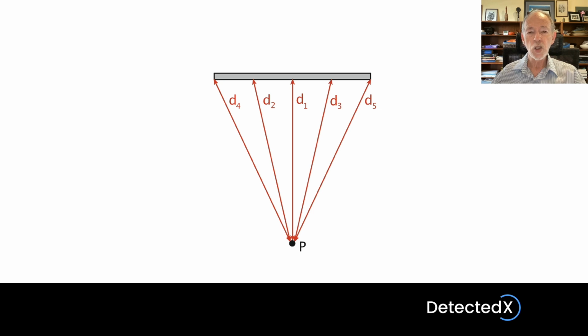Now let's think about geometry. Suppose I have a linear probe, and I am transmitting from different points on the face of that transducer, and I want to focus at the point I've labeled P. If I transmitted from every point on the face of the transducer at the same time, the ultrasound would travel along different paths to get to the point P. And I've labelled these path lengths D1, D2, D3, etc.